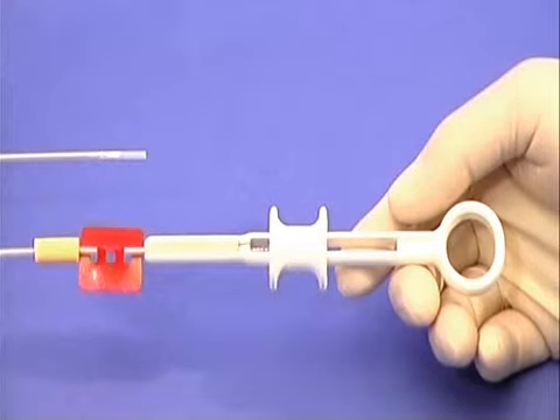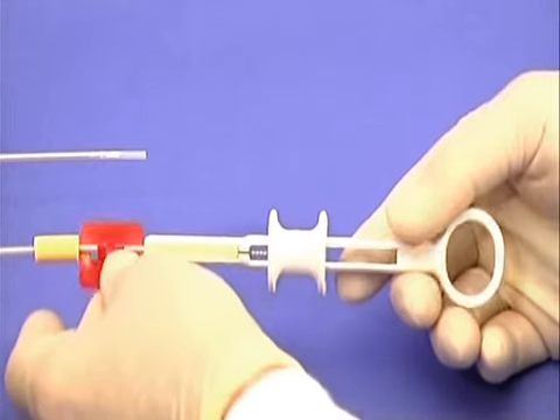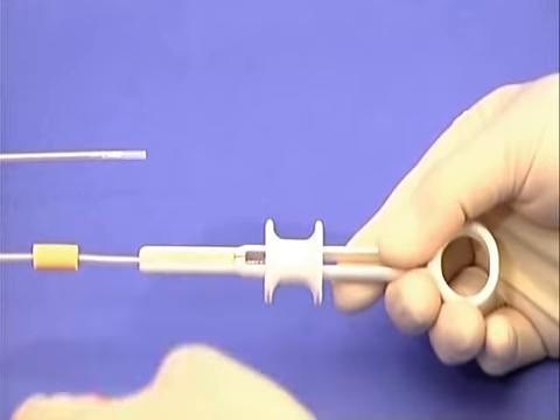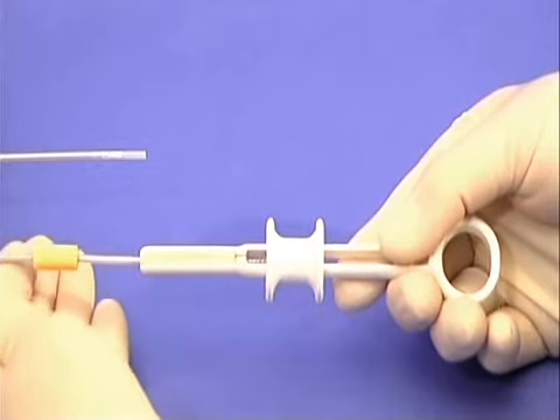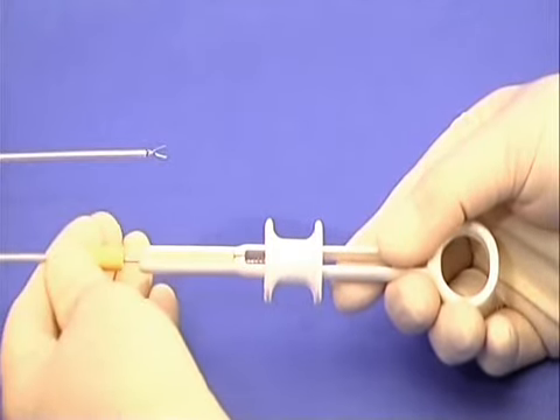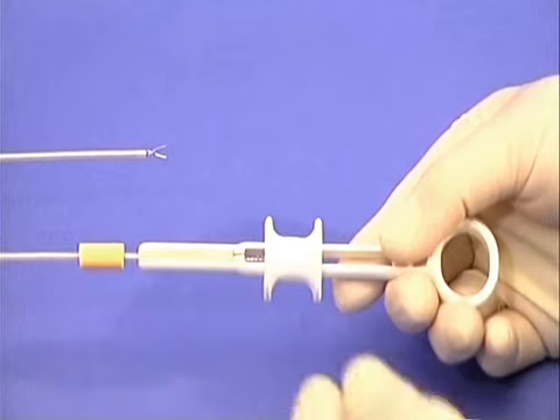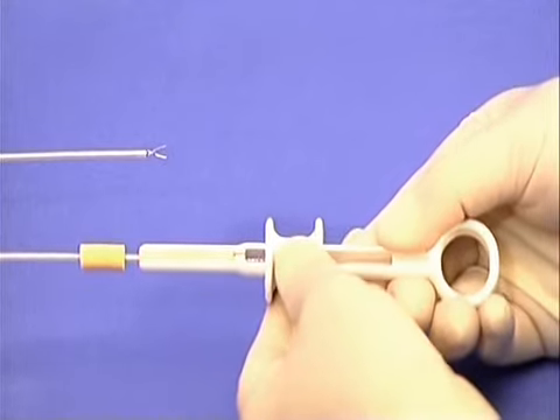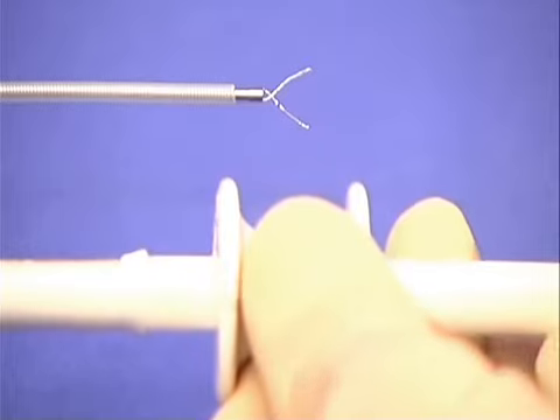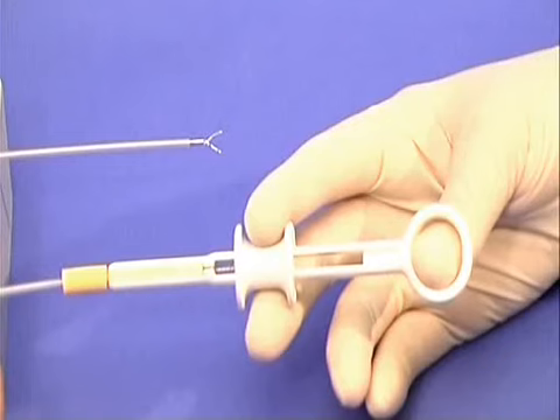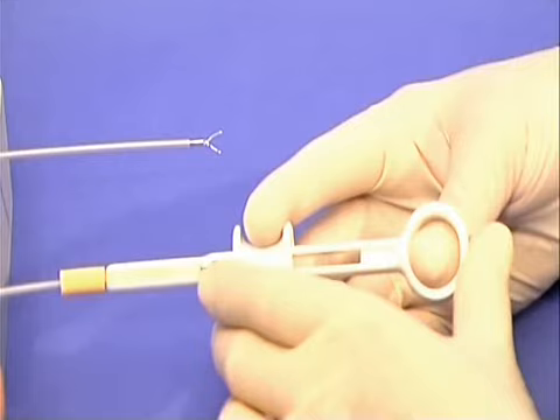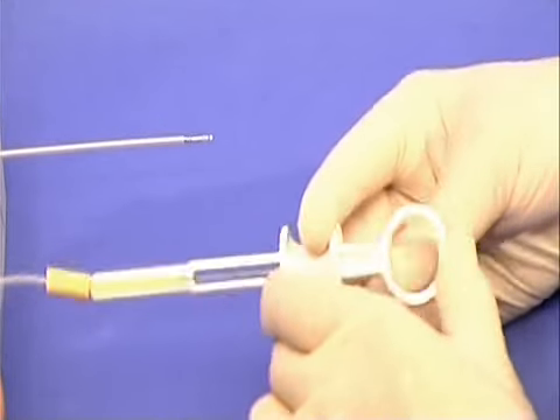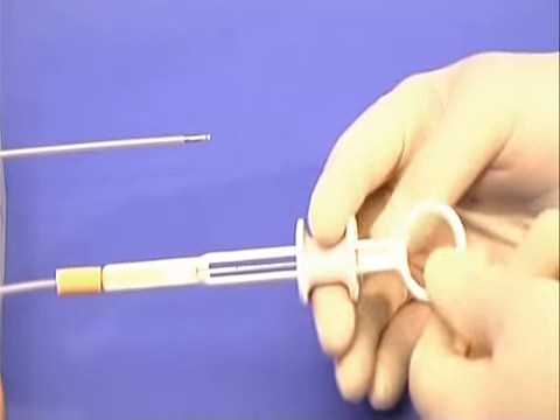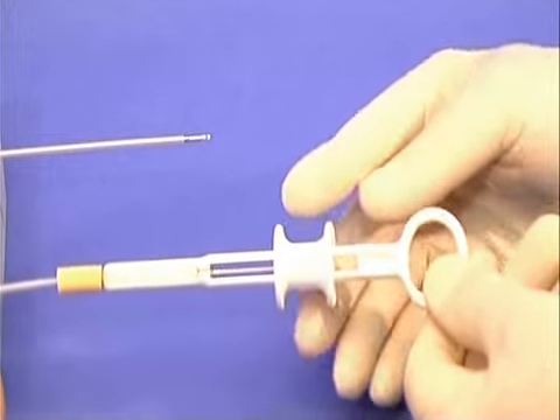The single-use quick clip is an important accessory to have available for emergency and very easy to use. Just take off the red packing spacer, pull back the outer sheath to expose the clip, squeeze the slider on the handle a little, which opens the clip, then squeeze the handle strongly, with 2 hands if necessary, to close the clip, and open the handle again to release it.